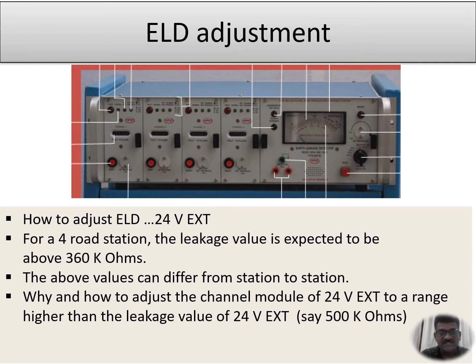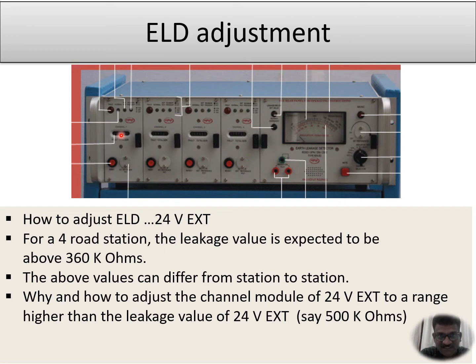ELD adjustment — how to adjust 24 volts external. Taking one example of a submodule: 24 volts external. For a 4 road station the leakage value is expected to be above 360 kilo ohms. This is a reference value given by RDSO, but it can vary from station to station depending upon the quality of the cables. Let us say presently it is 5 mega ohms, and we want to adjust 24 volts external to 500 kilo ohms.